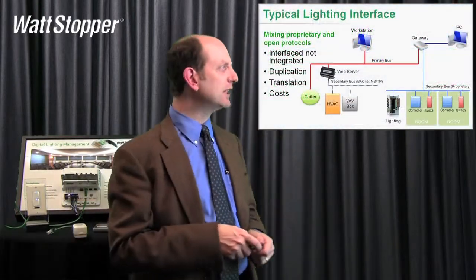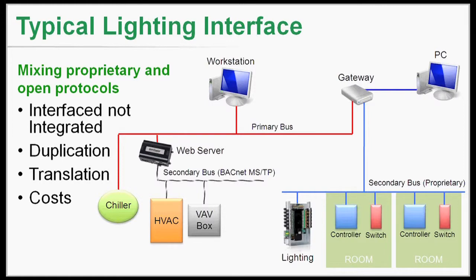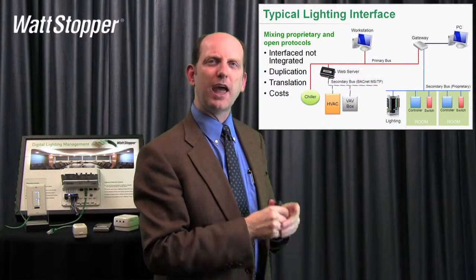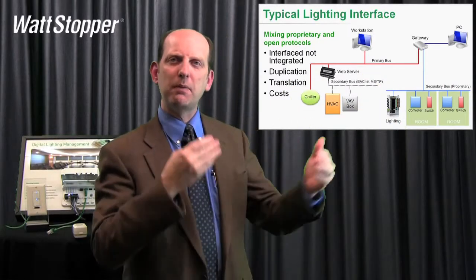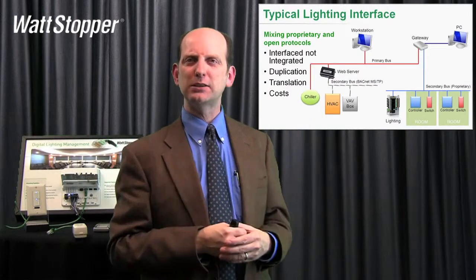Here we see a screen, and what we've got is what we refer to as the typical lighting interface. This is what's gone on before, and this is when somebody says they want an integrated building. One of the toughest words to really understand is 'integrated' — everybody might have their own vision of it. In this case, somebody said they wanted an integrated building, and what they wound up with was a workstation talking to a bunch of HVAC controls, and then a completely separate lighting control, and there's one box they call a gateway basically acting as a communication bus between those two.